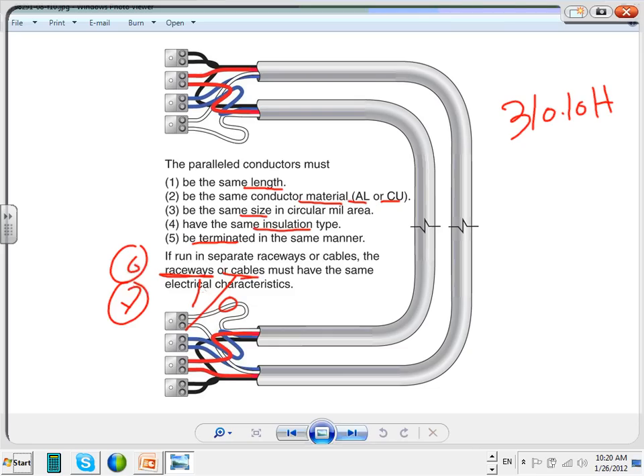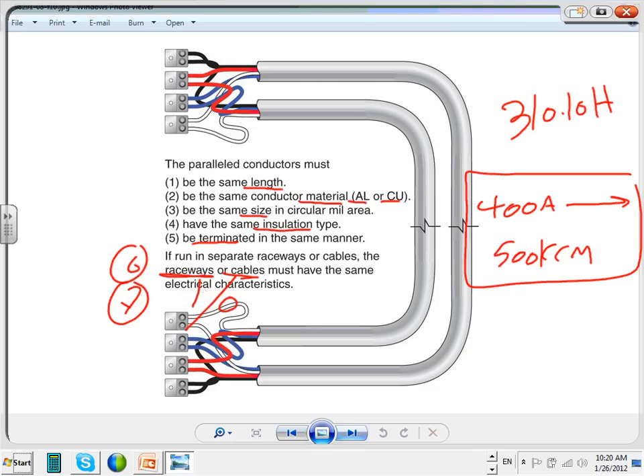So please remember that one, guys. Why would we parallel? Here's the recommendation. If you have 400 amp, that can lead you into 500 kcm conductor. If you have larger than 400 amp, that needs more than 500 kcm, it's smart to parallel. 500 kcm conductor, guys, because of the rule in the code, allows you to be tied to a 400 amp. So if I have a 400 amp panel, 500 kcm is good enough, because of the rule. If you go higher than 400 amp, or the load needs more than 500 kcm, parallel.